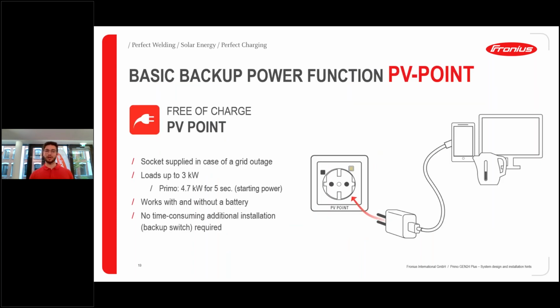Now we talk about the backup solution available with this product. And I want to start with the already mentioned and standard integrated one, which is the PV Point. The PV Point is the basic backup function, and we call it like that because you just have to do a single cabling onto a wall socket, and that's it. So from this cable connection that we saw in the inverter connection compartment, we just connect a single phase cable, grounding, neutral, and phase to a wall socket.